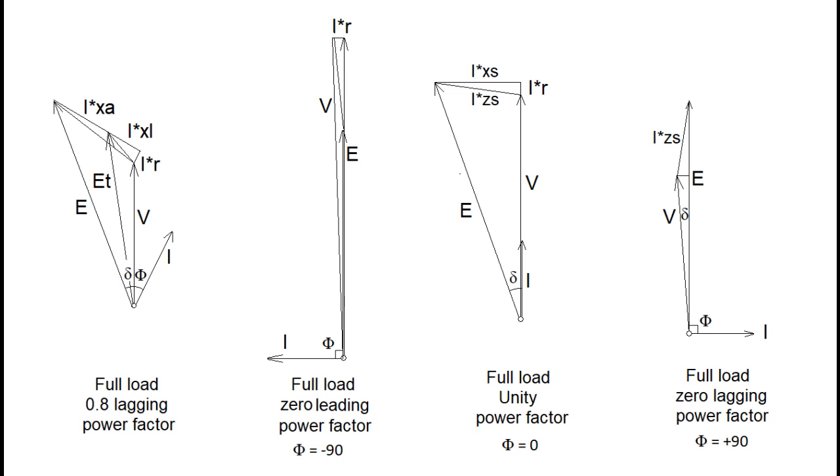The synchronous alternator that we have been considering from previous few lectures responds to rising load current and dropping power factor by reducing terminal voltage. This reduction is not expected but could not be avoided with constant excitation. Even with increasing excitation, keeping terminal voltage constant has a limitation due to magnetic material characteristics. This is how the region of the magnetic curve that the machine may use from no load to full load is decided. This decided portion of magnetic characteristics must be a linear part of the characteristics.